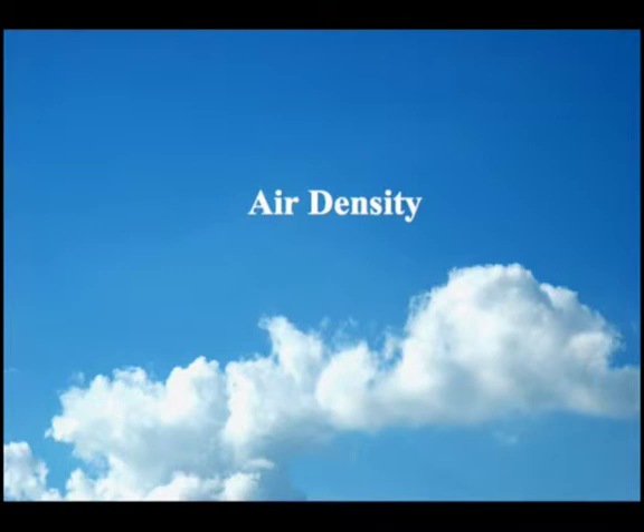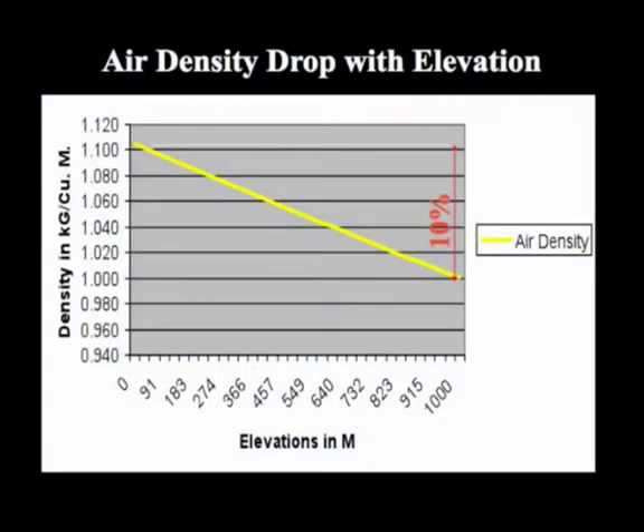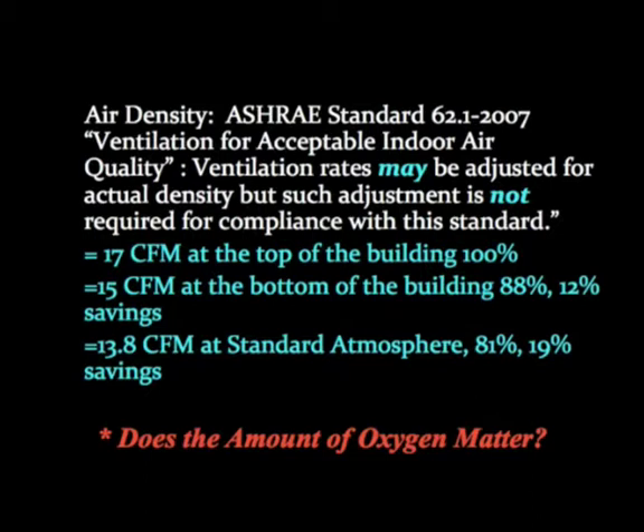Air density drops with elevation, as most of you may know, because the pressure drops with elevation. And that's why your ears pop when you get up to a high-rise building. This is interesting for those who are mechanical engineers, but even if you're an architect. Notice, don't worry about the unit here. That amount of ventilation air at the top of a 1 kilometer tower is 100%. At the bottom of the tower, because now the air is denser than at the top, there's actually more mass. Compared to the top of the tower, you got only 88% of that number at the bottom. And if you move that number to standard atmosphere, you got about 19% saving.